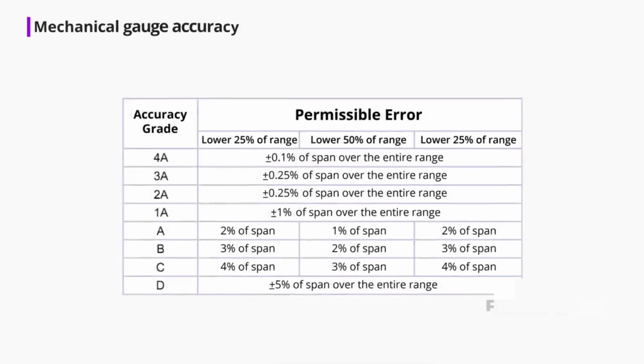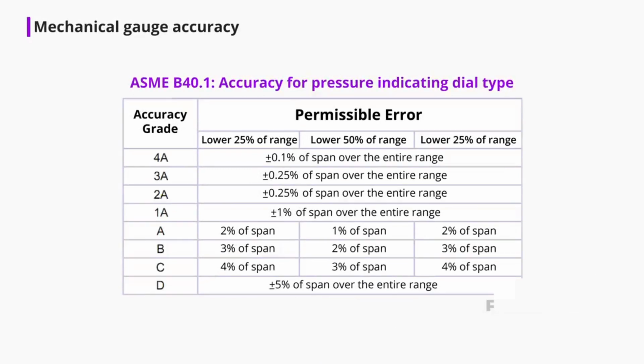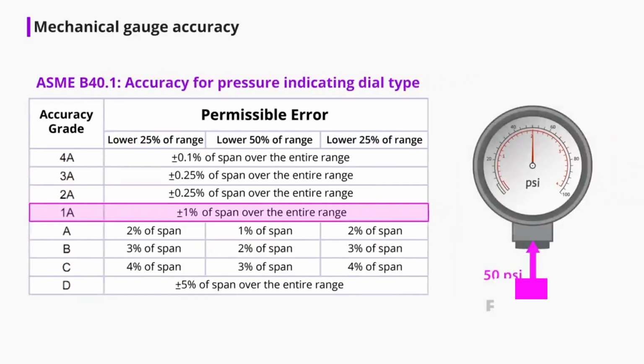The American Society of Mechanical Engineers ASME B40.1 standard defines the accuracy grades of dial-type gauges. Requirements differ from one industry to another, and the ASME B40.1 would be your guide for proper selection. For mechanical pressure gauges, accuracy is usually defined as a percentage of the entire span of the range. For example, a mechanical pressure gauge with a 1A accuracy grade has an accuracy of plus or minus 1%. With a reading of 50 psi on a 0 to 100 psi pressure gauge, the actual input pressure can be anywhere between 49 psi and 51 psi.